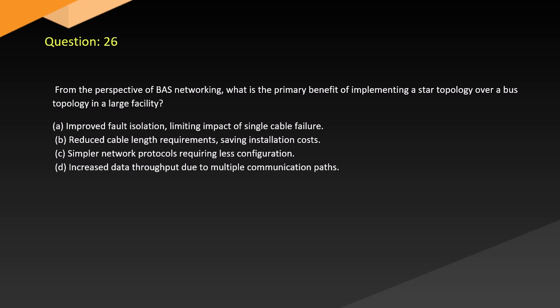Question 26. From the perspective of BAS networking, what is the primary benefit of implementing a star topology over a bus topology in a large facility? A. Improved fault isolation, limiting impact of single cable failure. B. Reduced cable length requirements, saving installation costs. C. Simpler network protocols requiring less configuration. D. Increased data throughput due to multiple communication paths.